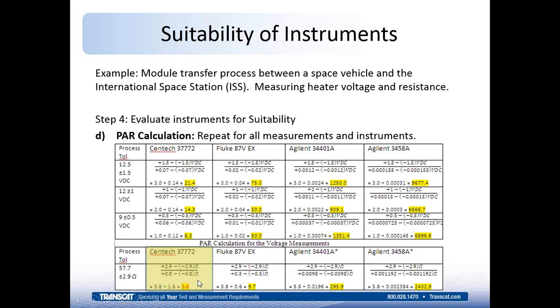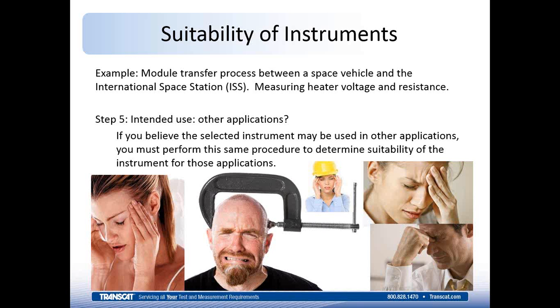So another thing to consider once you've gotten all those process accuracy ratios figured out, and you're trying to determine which instrument to use, another factor you might pull into play is what are the other applications that instrument might be used for in other places in the production plant. If it's going to be used somewhere else, then you've also got to do that same process for where that's going to be used. Or if you're thinking about down the road where an instrument might be used, you might want something that's a little more robust in that PAR calculation so that you don't run into low accuracy ratios down the line.